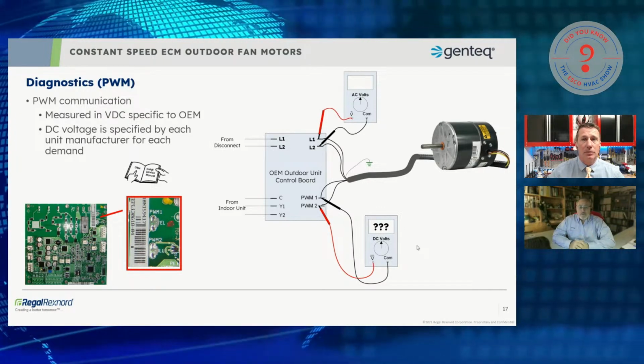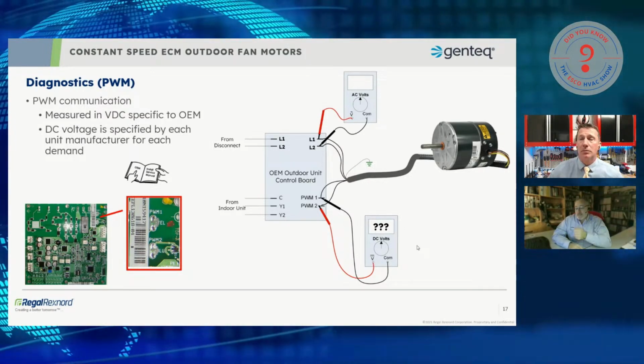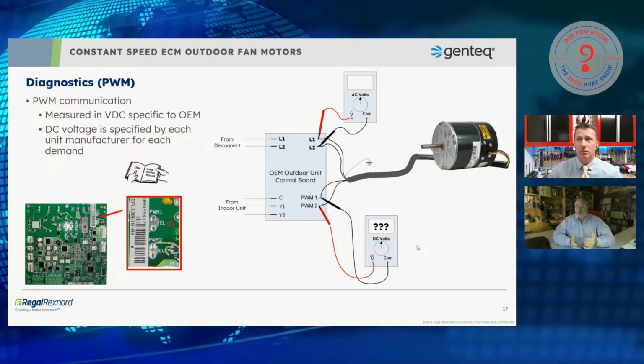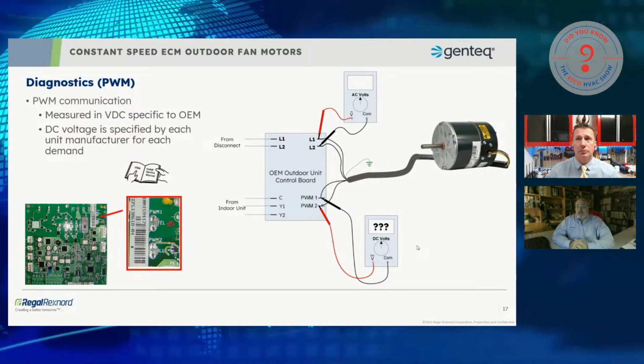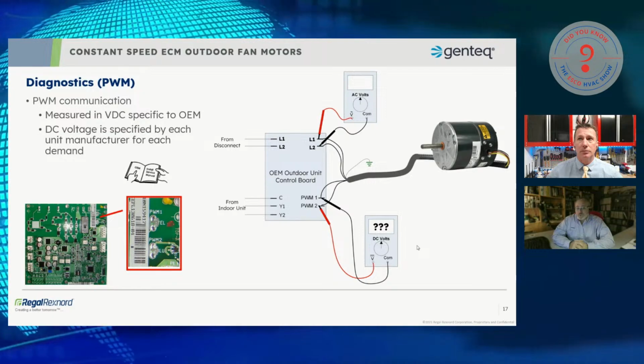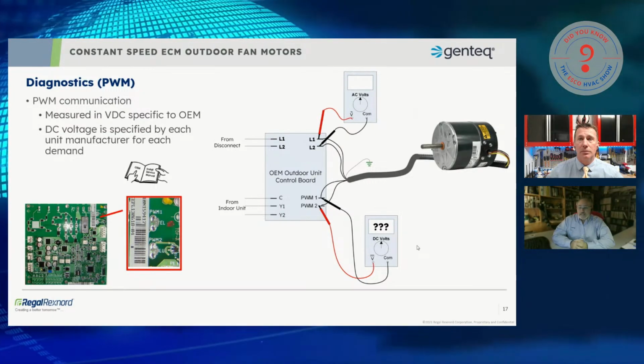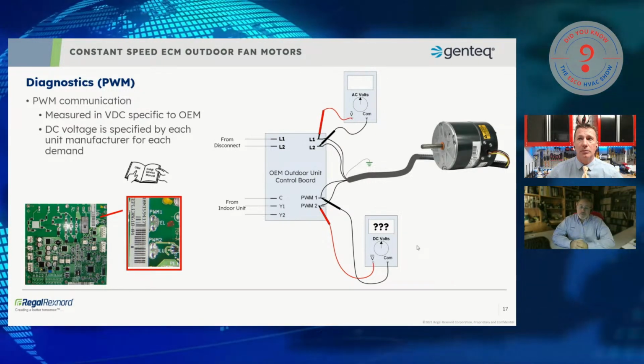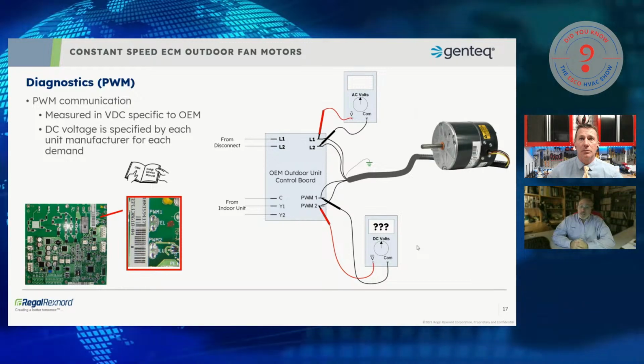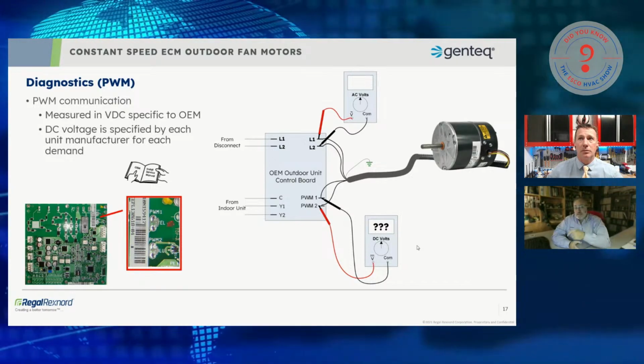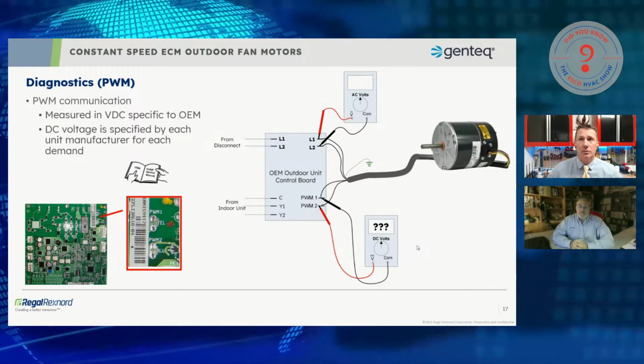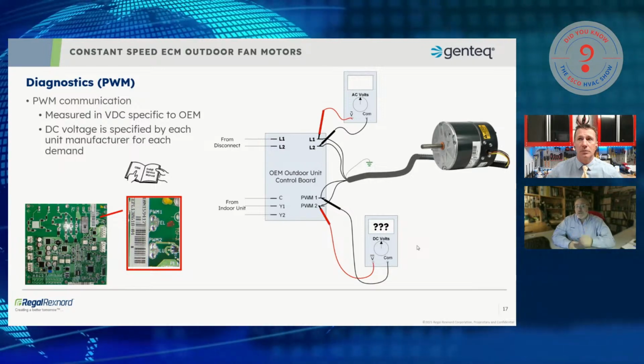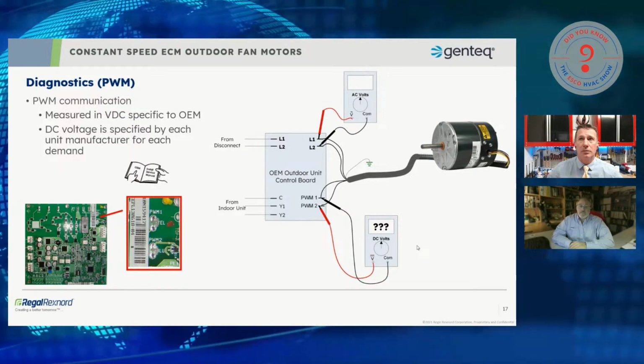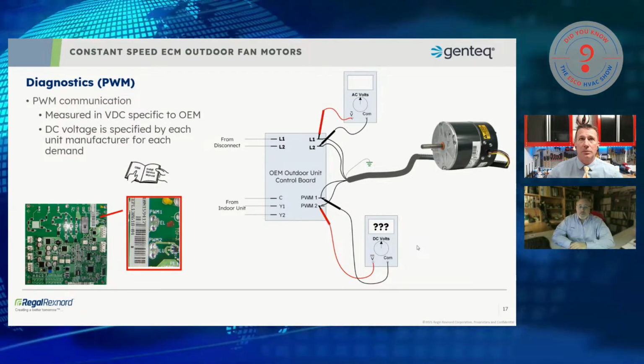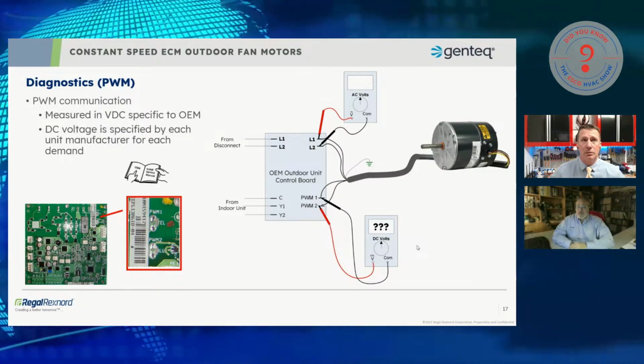The motor should be operating. And if that voltage is what the manual says it should be for either first or second stage, that also means I should have the correct airflow for whatever stage I am in. Many manufacturers with PWM will also provide a low ambient speed, and that's going to again be typically a lower PWM or DC volt value than your first stage. So if you do have low ambient controls and you're in low ambient mode, be aware.